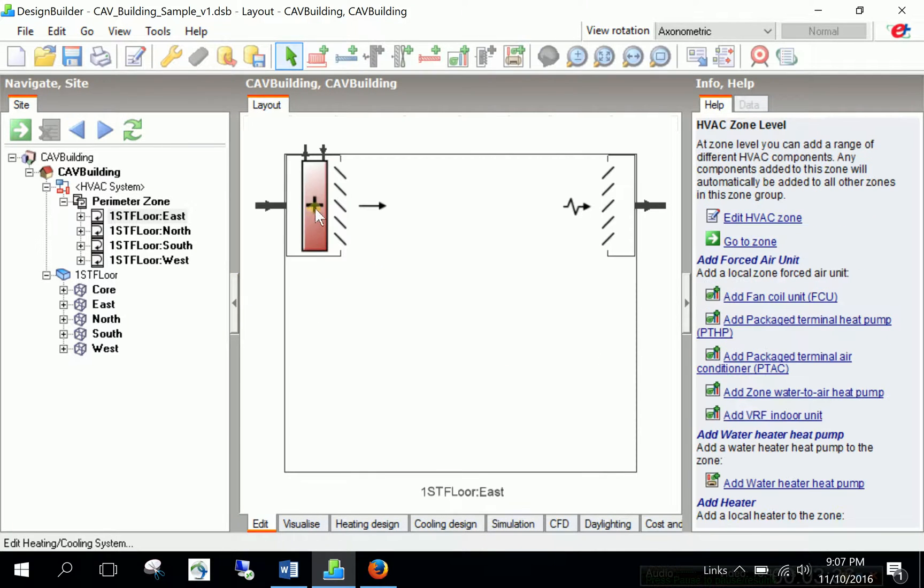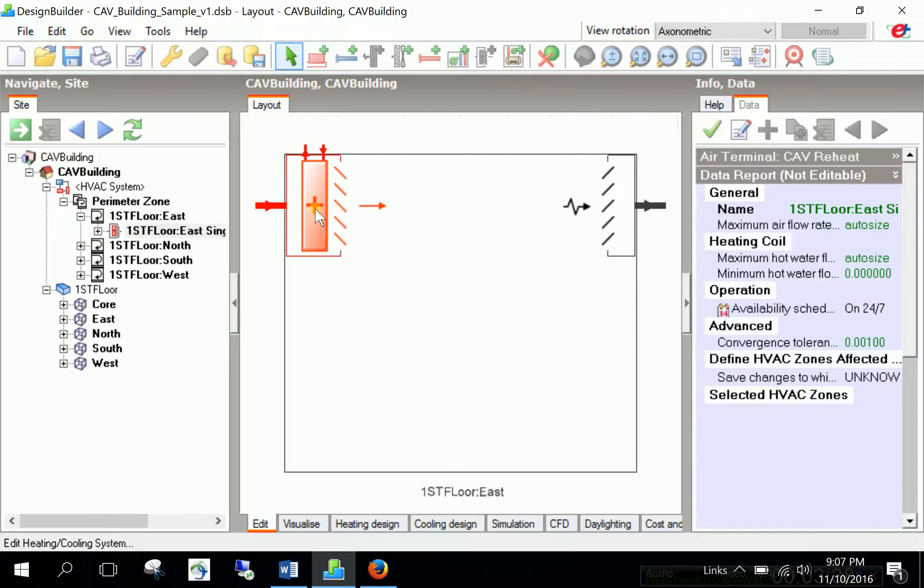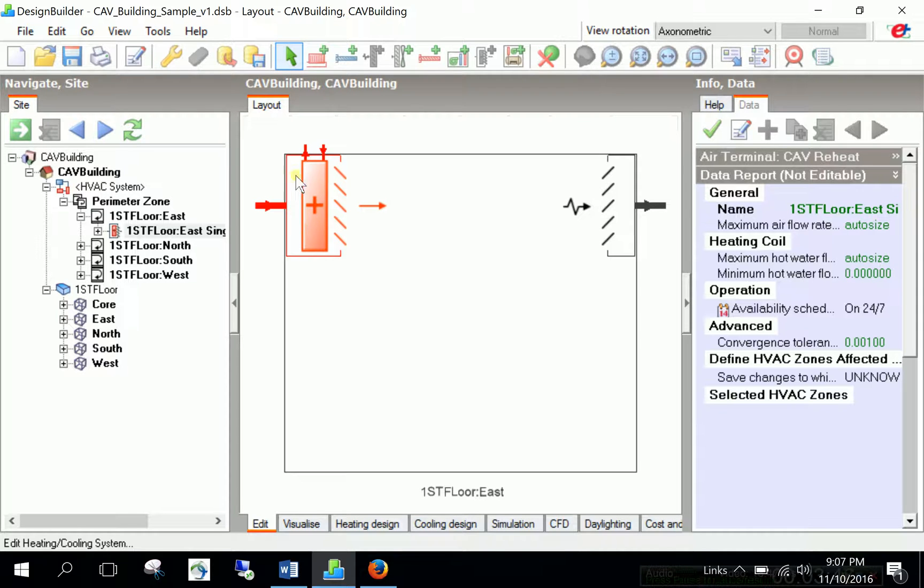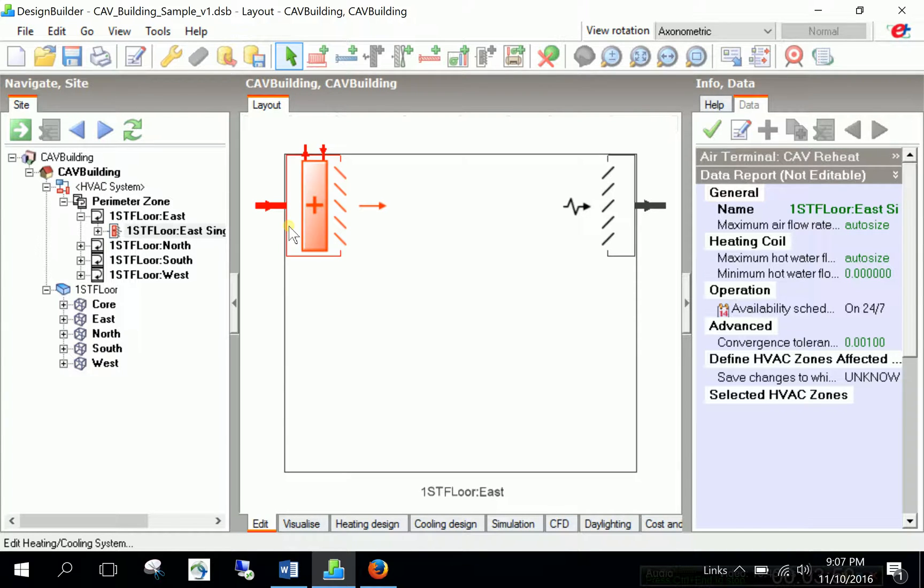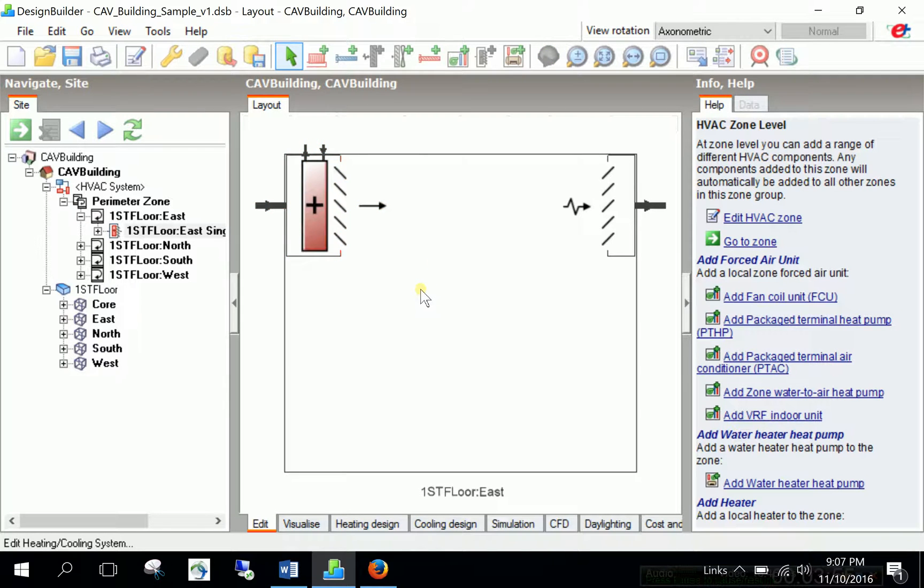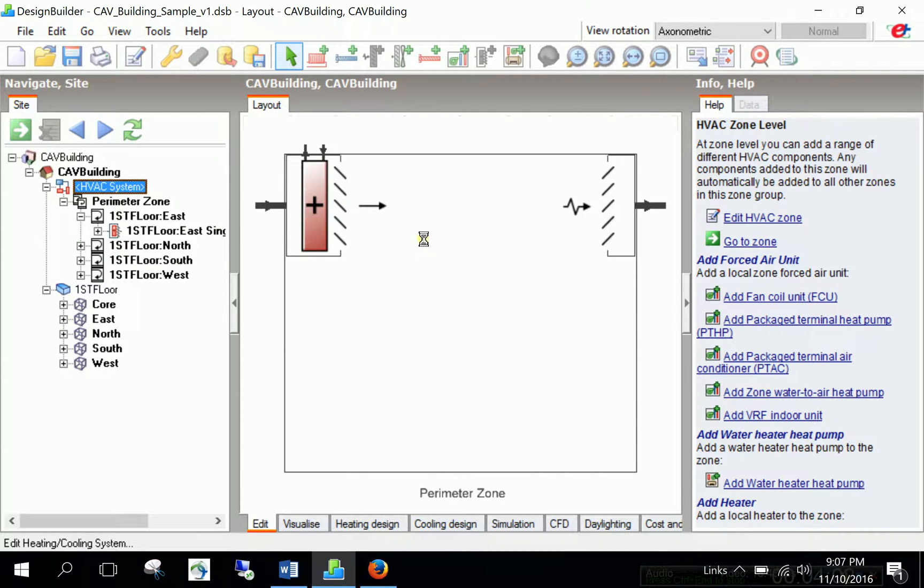And then click again and scroll down a little bit and you will see zone extract. So, please click on it and drag and drop to the zone group. OK. We added our CAV reheat system. And in the Perimeter Zone, we see that all the thermal zones in this list, in this group, has the same air distribution unit. But please pay attention to this reheat CAV reheat type. We don't have any dampers here. If you compare with the VAV system, we have some dampers. And these dampers are adjusting the volume of air supplied to the zone. But at the CAV system, there is no such thing.